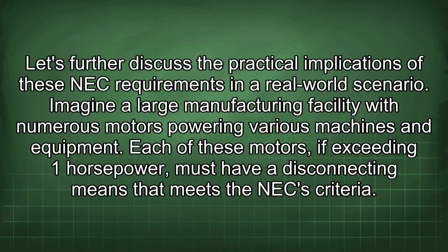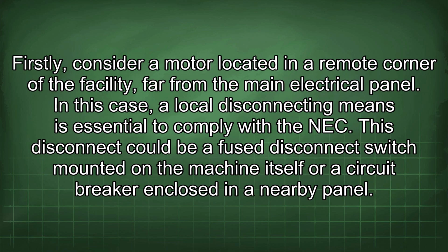Imagine a large manufacturing facility with numerous motors powering various machines and equipment. Each of these motors, if exceeding 1 horsepower, must have a disconnecting means that meets the NEC criteria. Firstly, consider a motor located in a remote corner of the facility, far from the main electrical panel. In this case, a local disconnecting means is essential to comply with the NEC. This disconnect could be a fused disconnect switch mounted on the machine itself or a circuit breaker enclosed in a nearby panel.